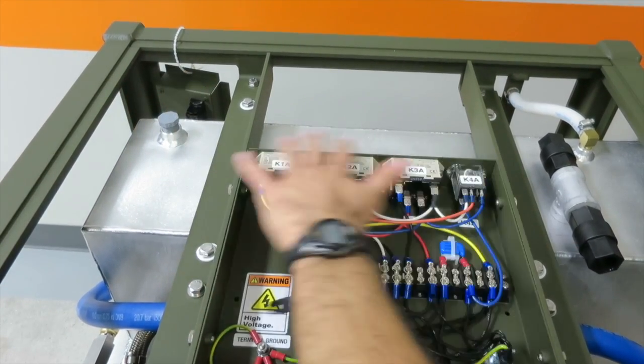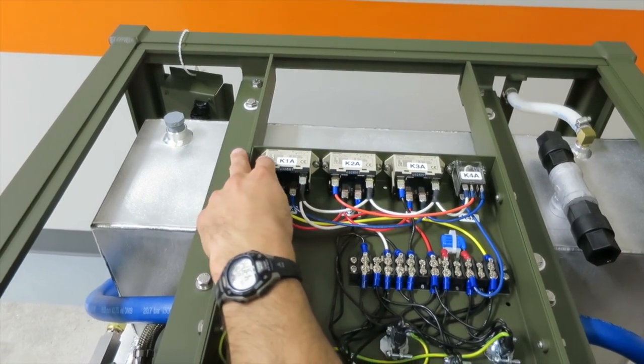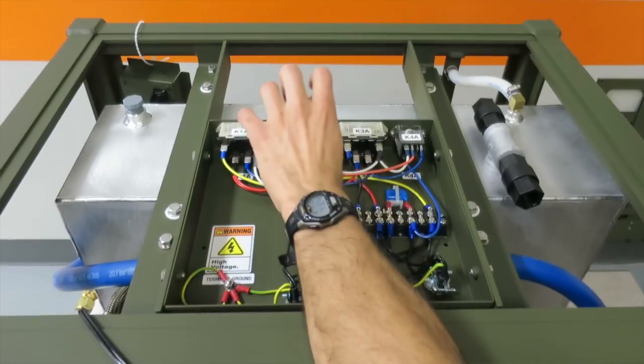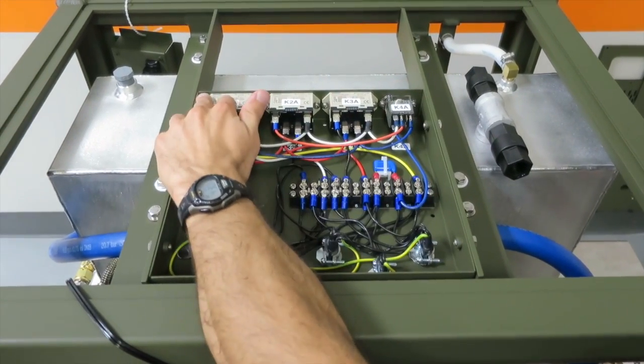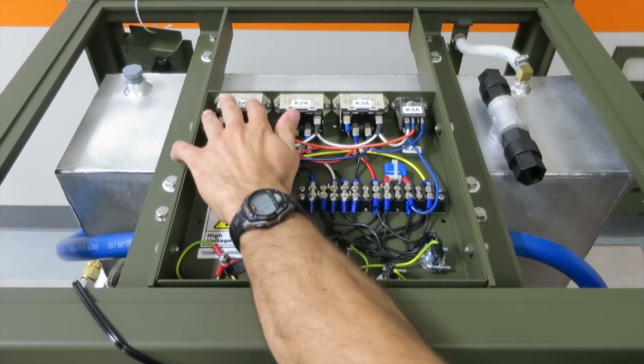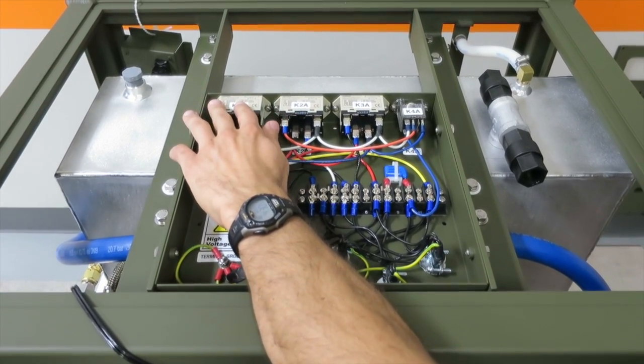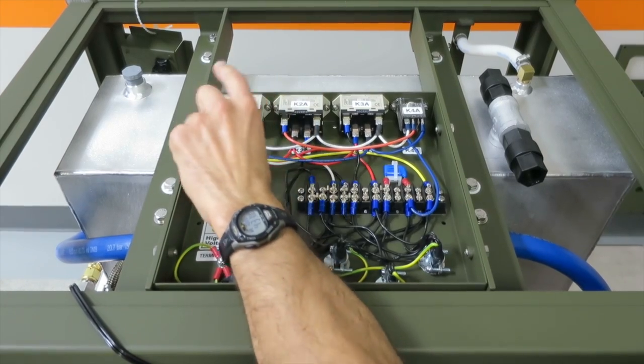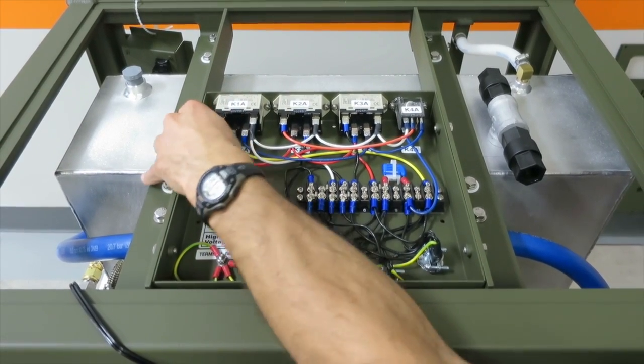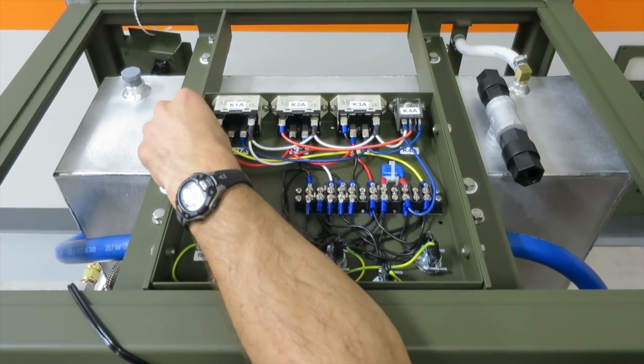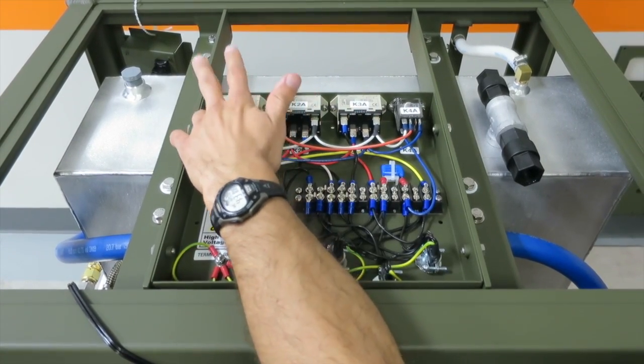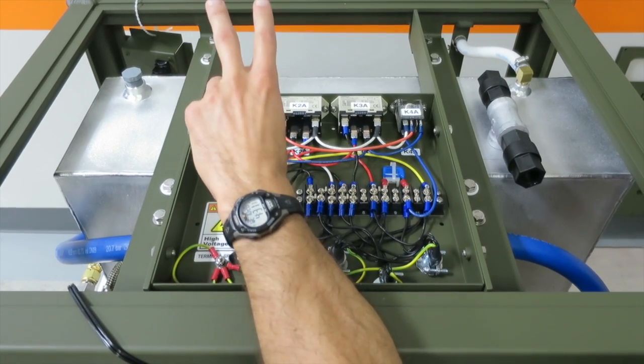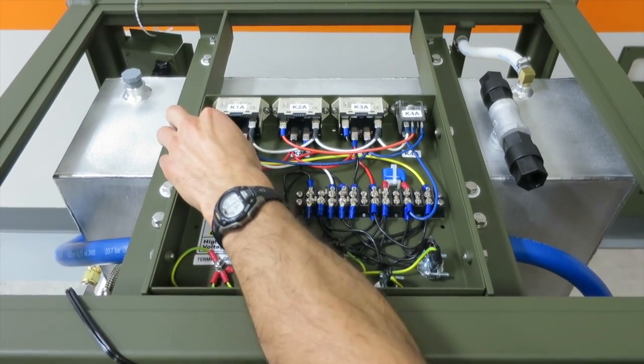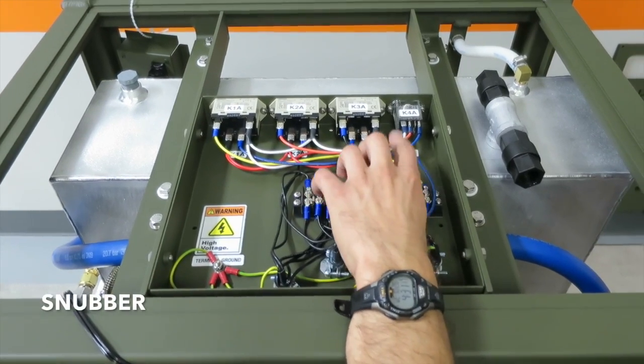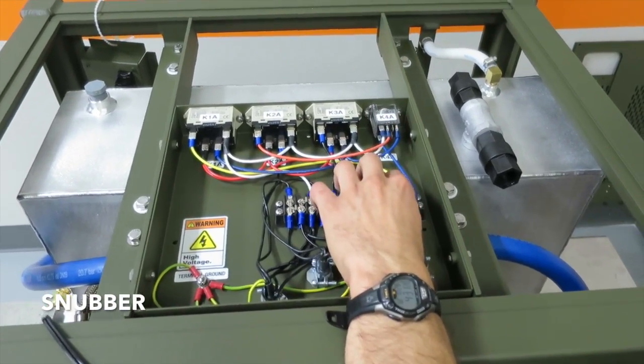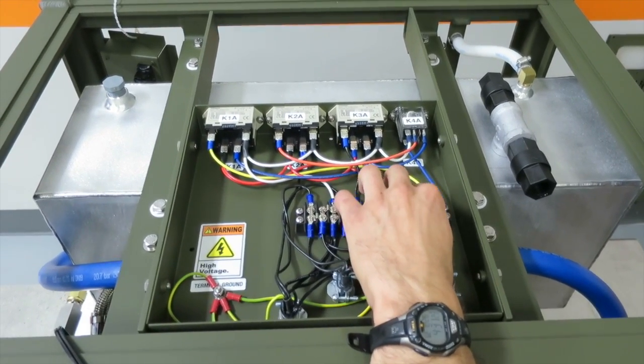Now here in the electrical box, here's all the electronics controlling the water recovery system. So we have K1, K2, K3, and K4 relays. And these all work in conjunction to turn the pump on and off, whether you're pressing the toggle switch or the sterilizer main unit is telling the water recovery system to turn on. So these all work together to turn the pump on and off, and then also to open the fill and recirculation valve. Right here is a little snubber that protects the liquid level switch. So it's kind of protecting it from any voltage spikes.